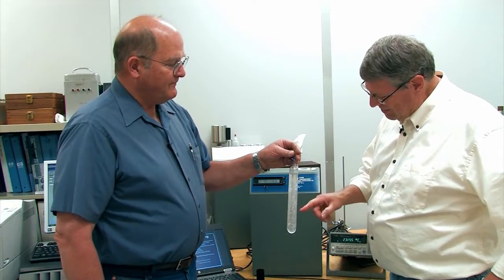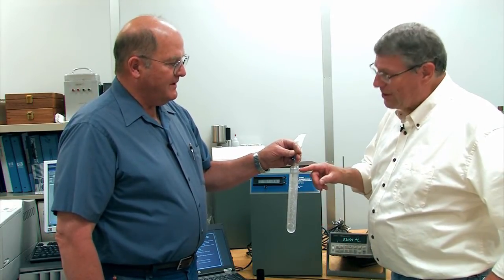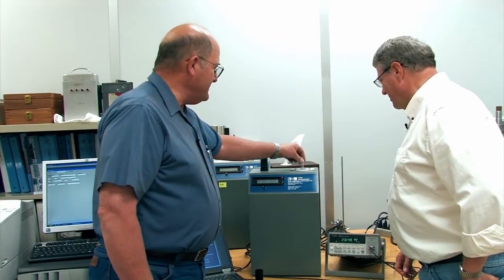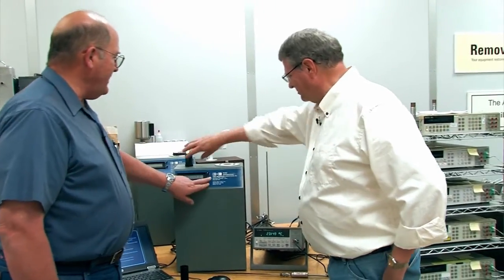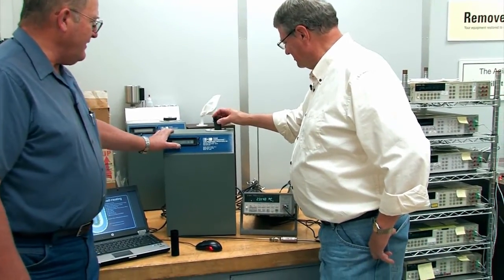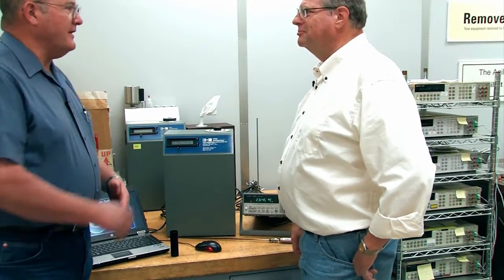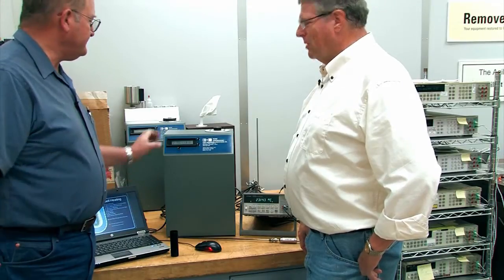Okay, so we've got ice, we've got water, and we've got not air. We've got vapor. Yes, good. All right, so we put it back in. That cell will go back in the maintenance system. We'll change the set point from -8 up to a value that will maintain it for approximately 8 hours. And then we can use that instrument to make actual measurements. Okay, well, let's try it.